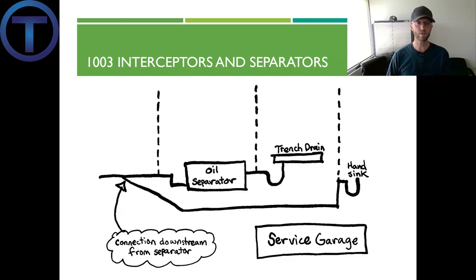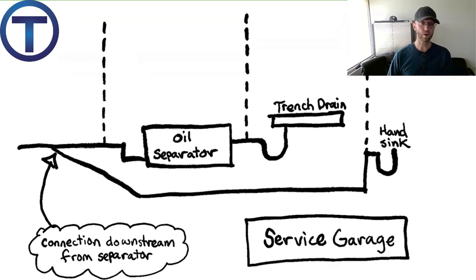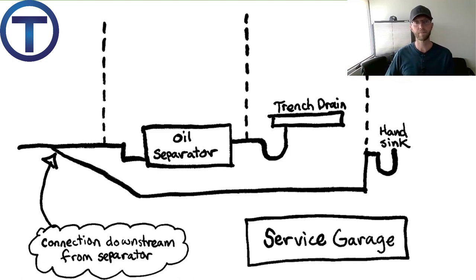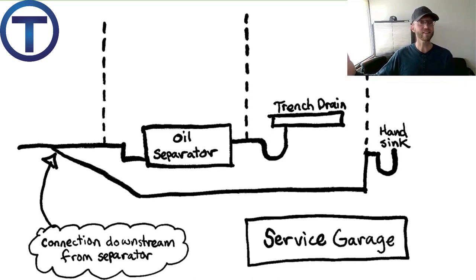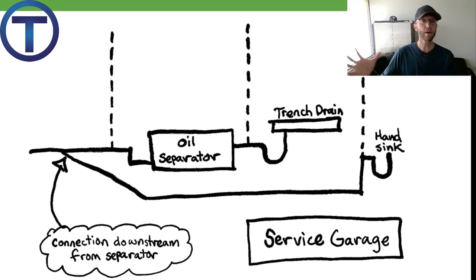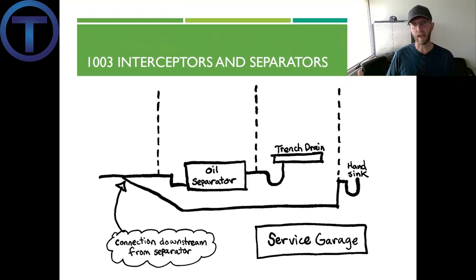Here's an illustration of that. We have a trench drain and an oil separator in a service garage. In the same garage, there's also a sink for employees to wash their hands. The trench drain may receive oil or other liquids that need to be separated before going down the drain, but the sink is just soapy water. So it should be piped so it does not pass through the oil separator — we don't need to put any more waste through there than absolutely necessary.